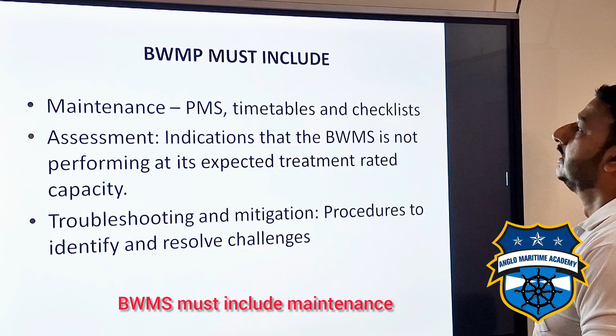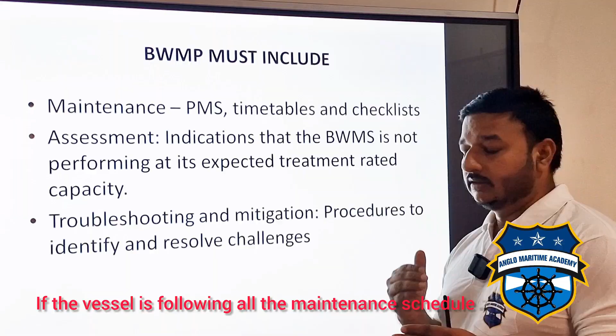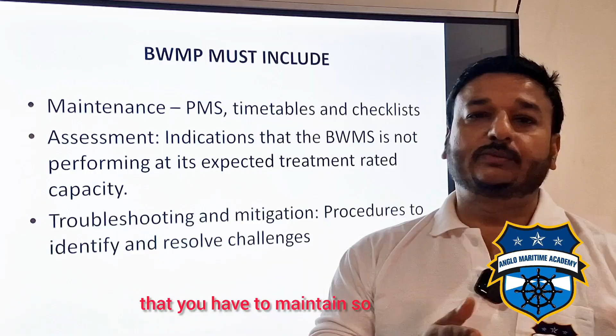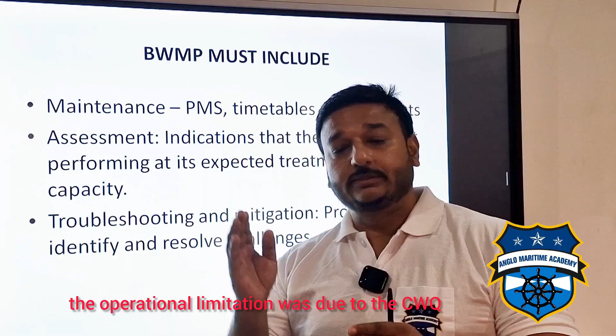Okay. BWMS must include maintenance. So maintenance is a very prime aspect here. If the vessel is following all the maintenance schedules, all the PMS schedules, all spares are being replaced on time, manufacturer's guidance is being followed, and all the checklists, maintenance and services are being done on time, then you can prove that the alarm, the problem, the operational limitation was due to the CWQ and not because of my equipment. Your equipment is only working properly as long as you are maintaining it in the correct order as per the manufacturer's instructions.